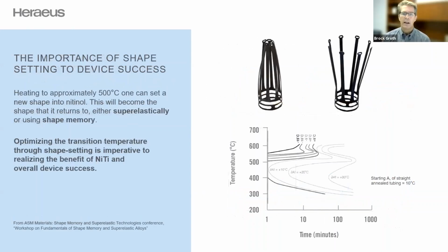Move on to the next slide. In the interest of time, we're going to go very quickly on this slide. What I'm going to say is there's a range of temperatures that you can use to shape set your device, and that will affect the transition temperature of the device. So at the top on the right, you've got a shape set, conical shape. On the left is what that device looks like coming off the laser cutter. The tines or the legs curl in and touch one another, and that's just residual stress in the tubing or heat affected zone, things like that. That's not a problem. You can shape set it as you need, but in doing this shape setting, in the lower right hand graph, you've got some very unusual curves.